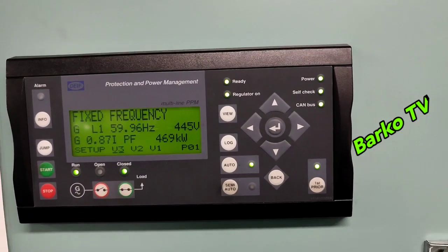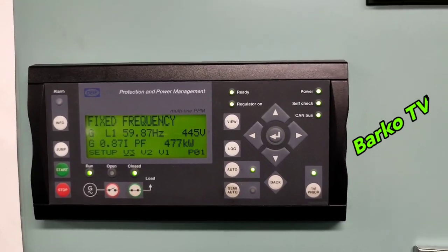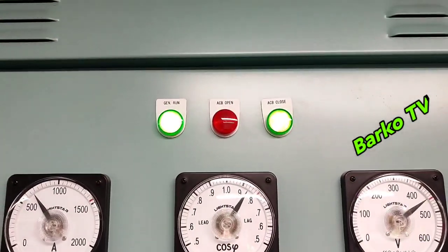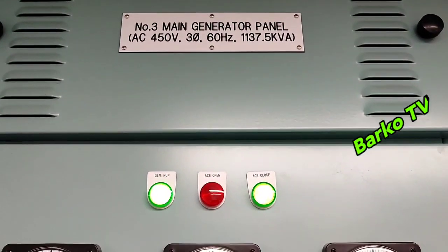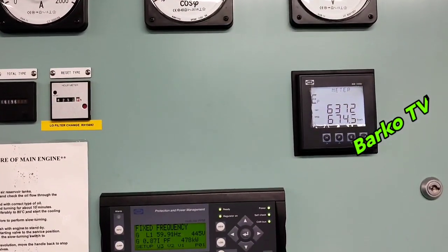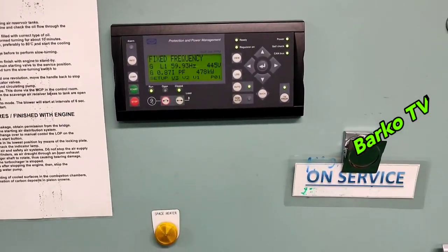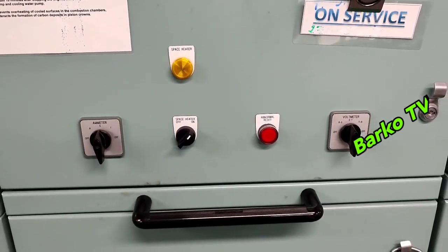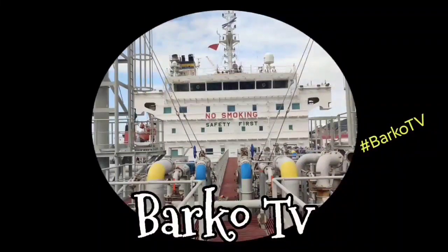After securing all bolts, nuts, connection terminals, and the fuse, put everything back and start the generator. The generator is already started and the voltage is normal — all parameters are the same since we performed the IR test. If you learned from this video, please like, share, and subscribe, and don't forget to hit the bell for more updates. Also follow us on Facebook — Barko TV. Thanks for watching.